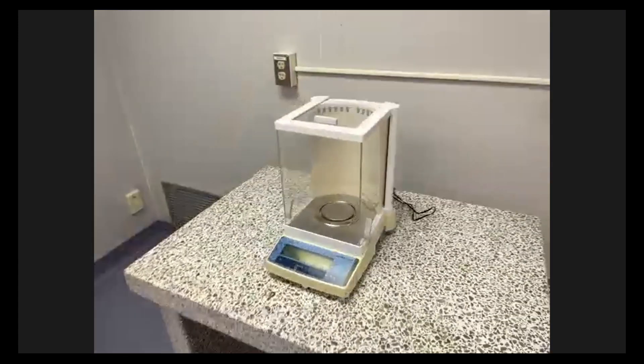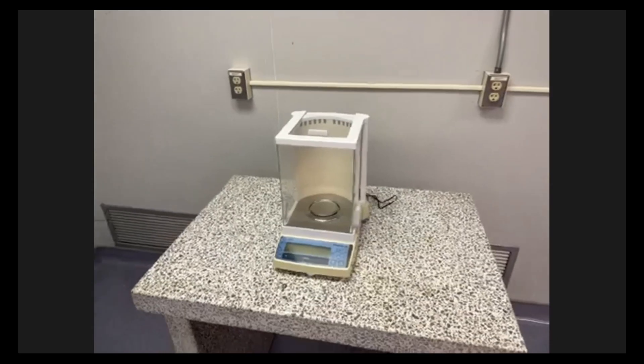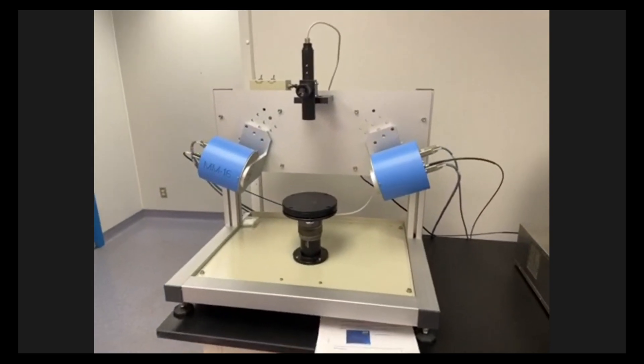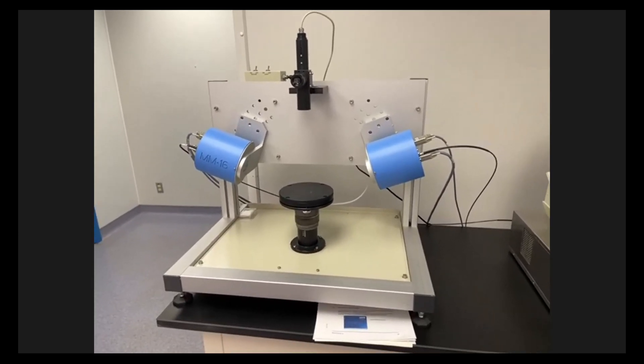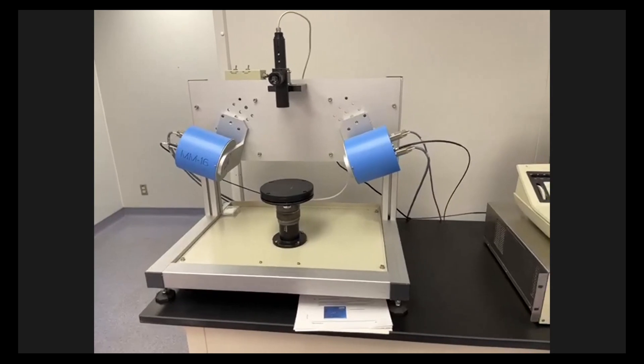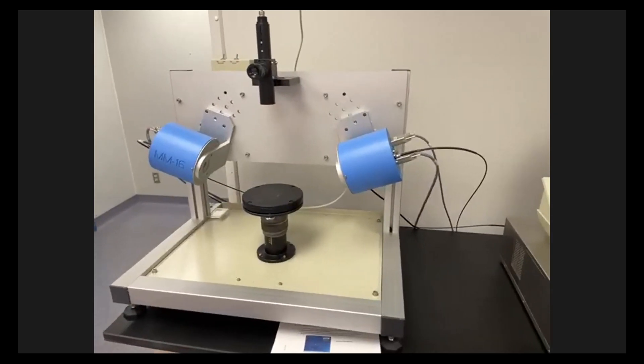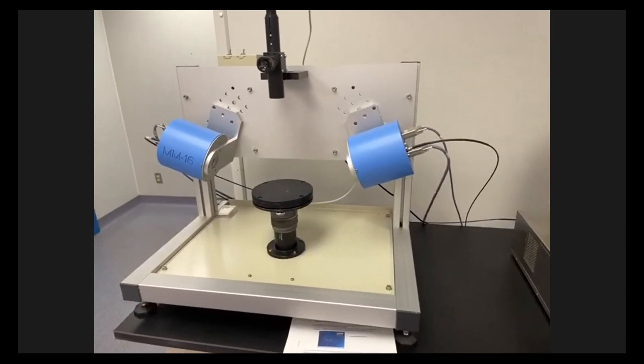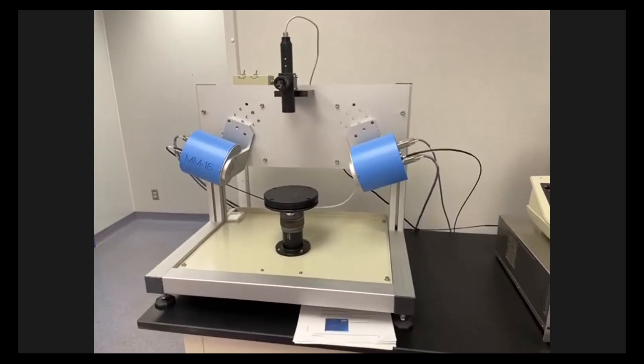We also have a high precision weighing scale, as every lab needs one. Next we're going to the ellipsometer. This is a really interesting device — it uses laser beams and is able to measure film thickness down to the nanometer scale, and also measures the optical properties of films such as refractive index. This is important when you want to find out the film thickness, especially for dielectric films. It's a crucial machine for characterizing optical properties such as refractive index of the films you're depositing.